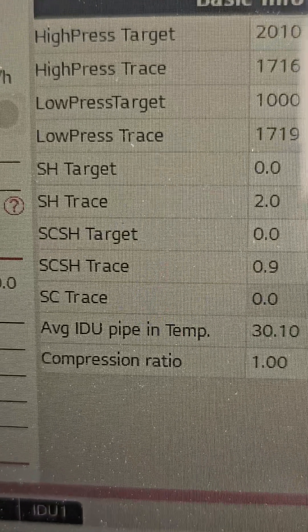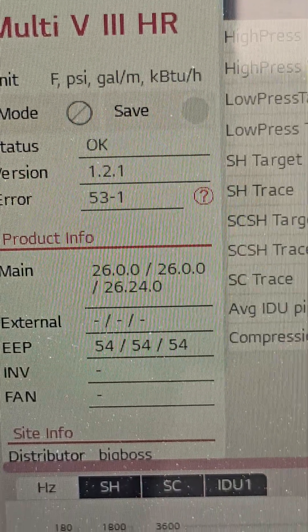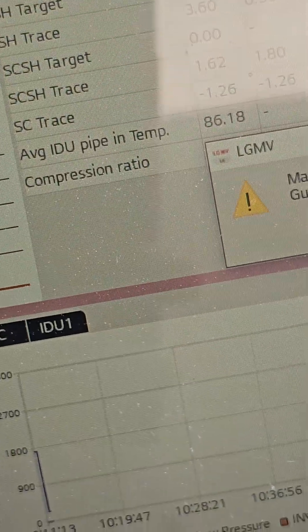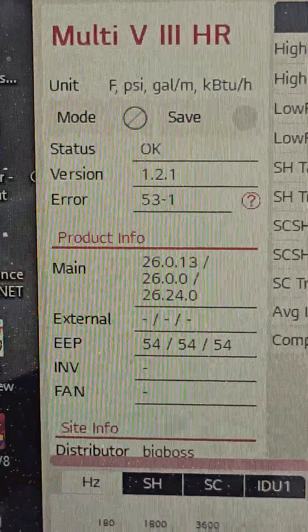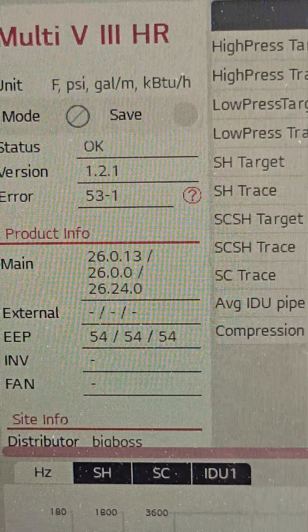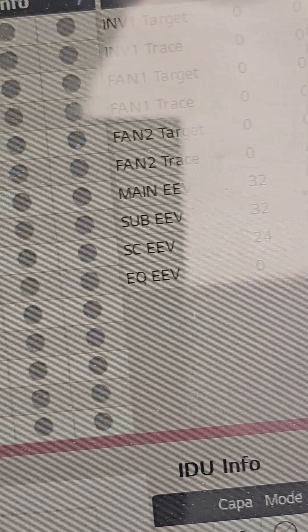We're in, just like that. Let's zoom in on the data. Status: okay — it means we're connected. We have one error code. I don't want to do any of that. Manual. Okay, that's what it is. So there's everything. Error code 5053.1. Let me put a full screen on this. There it is — that's better.